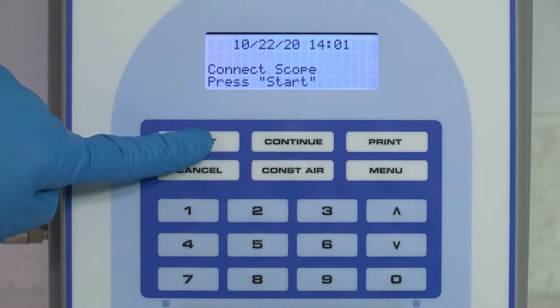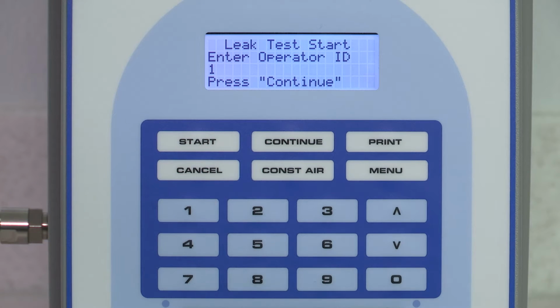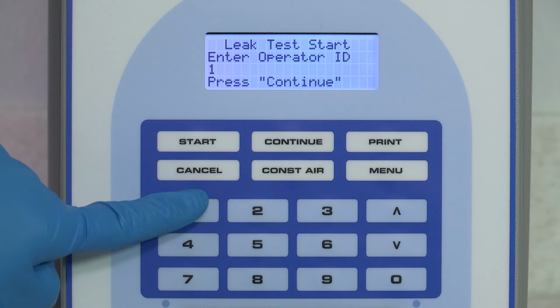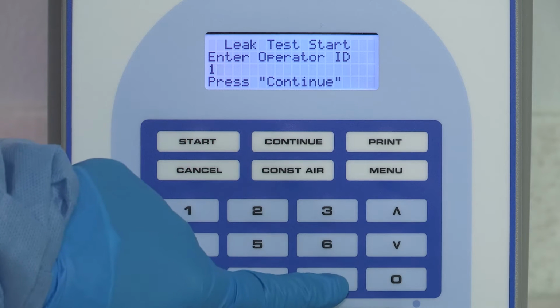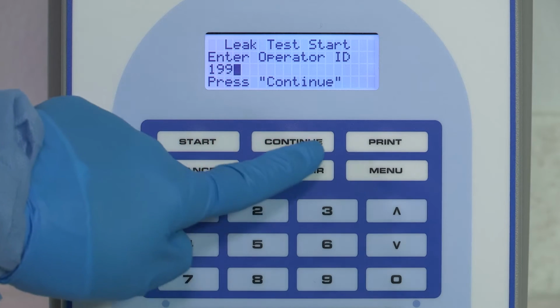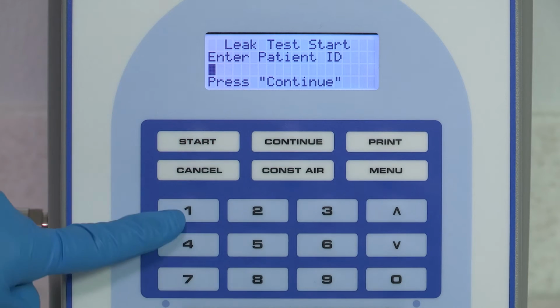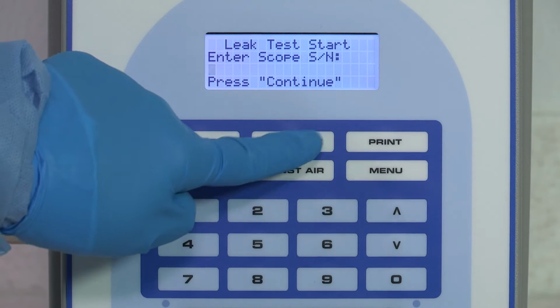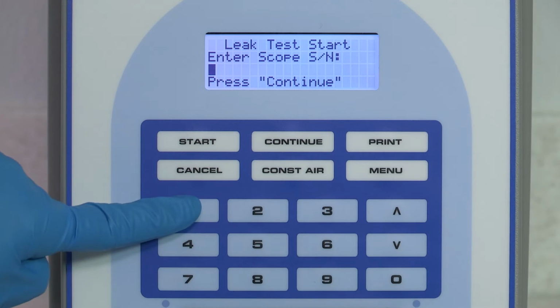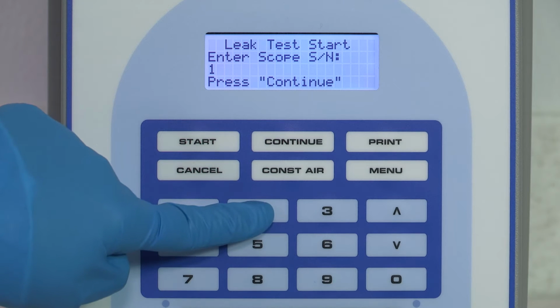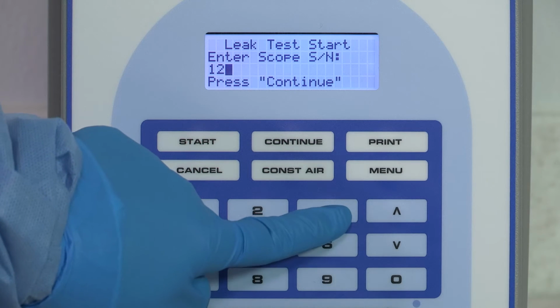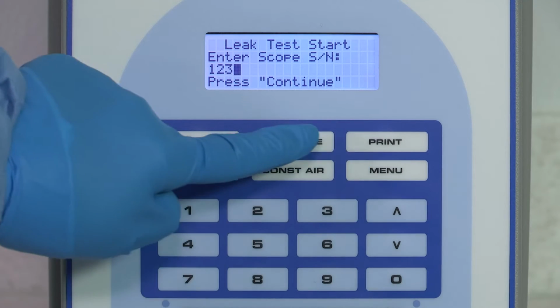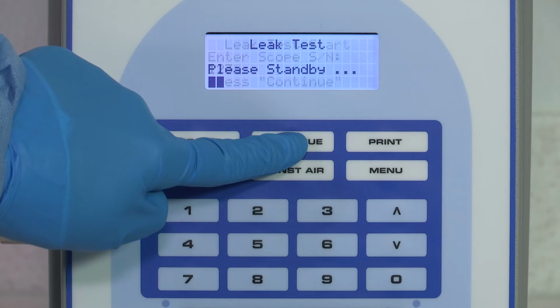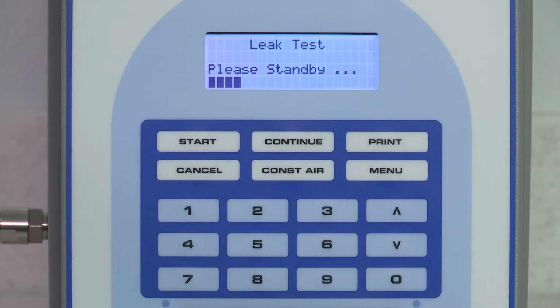Press the Start button on the touchpad to begin the QA test. If prompted for operator ID, enter the operator ID using the numerical keypad. If the patient ID displays, press Continue. No information needs to be entered at this time. When the Enter Scope serial number prompt displays, enter 123 for the code for the quality assurance test. Then, press Continue. The leak test automatically begins.